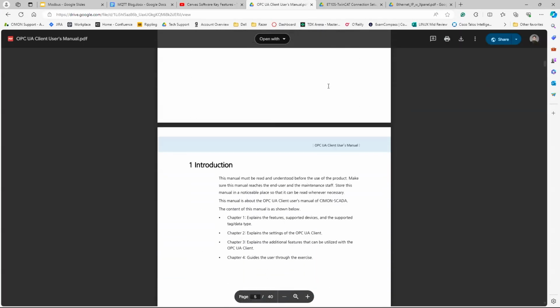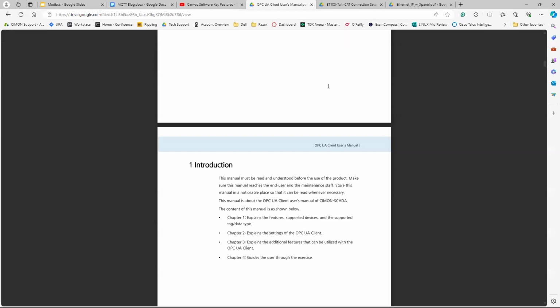So we have a couple devices that support OPC UA. We have OPC UA server on our PLC. Yes, you can use it, but it is not up to date on the certificates. So if you're using something like Kepware, that always stays up to date on certificates. It might not communicate effectively, but our HMI, the NXT-EXE, is always up to date on the certificates, and so is our SCADA software. So we have two interfaces that really take advantage of OPC UA server and client. Our SCADA software can be both, and our HMI can be both an OPC UA client and server.